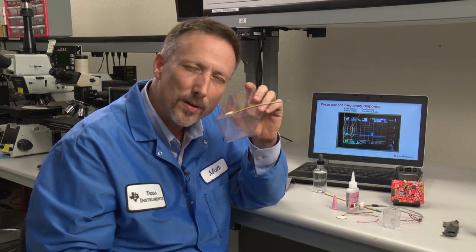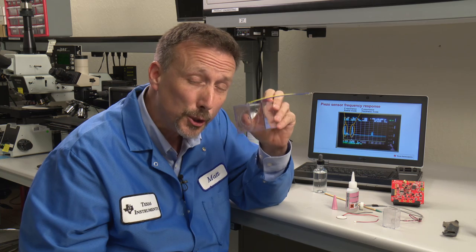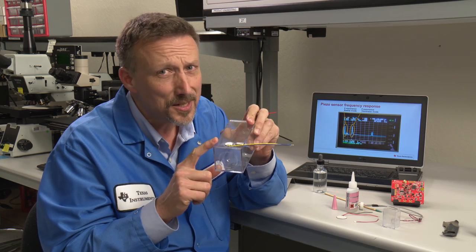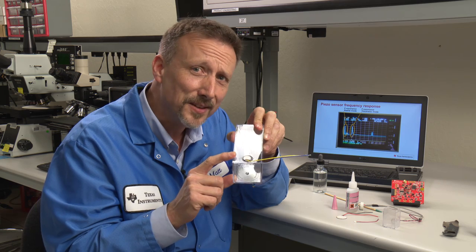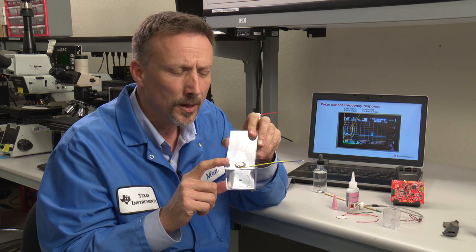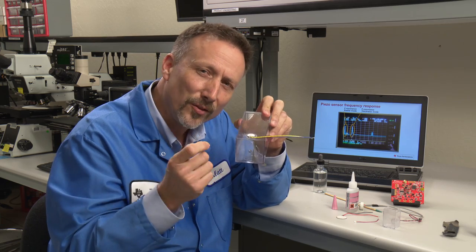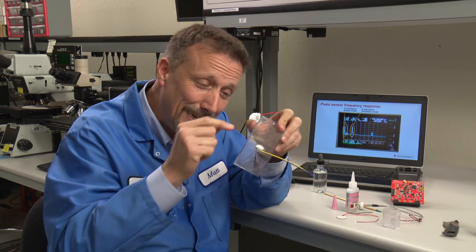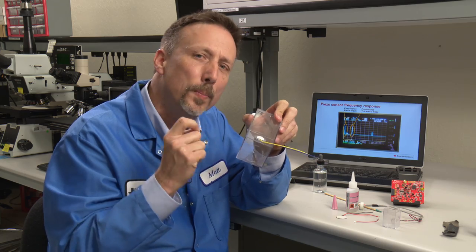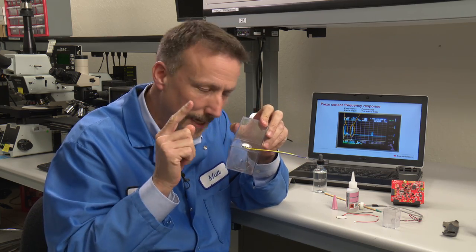It's an important note to make sure that you actually glue it onto the container. We've had some folks that have tried less effective methods, taping, etc., or using rubber glues. They'll just take away from the energy that gets put into the container and you won't be able to receive your echoes. Glue is the key.